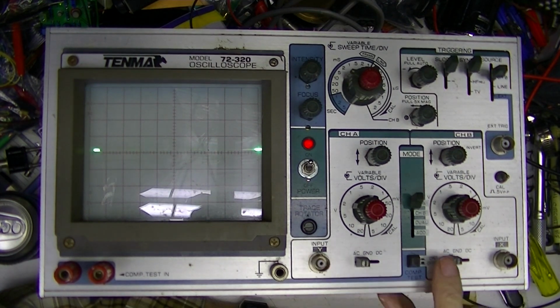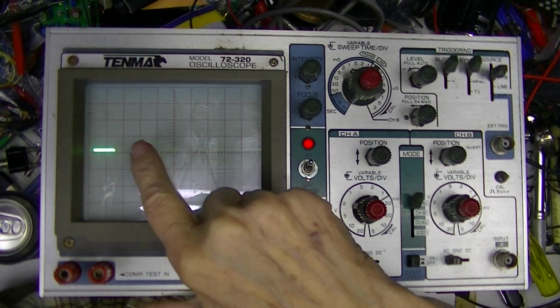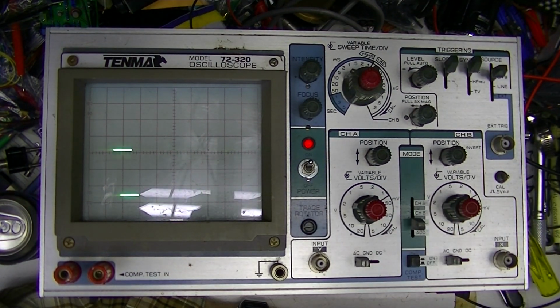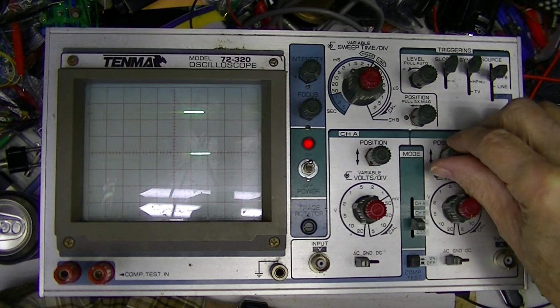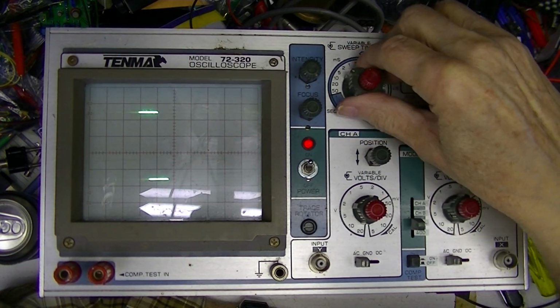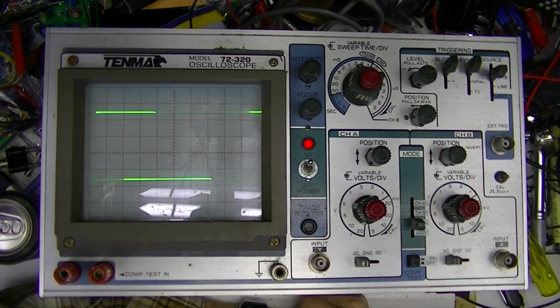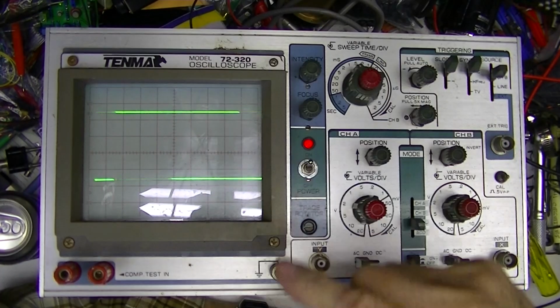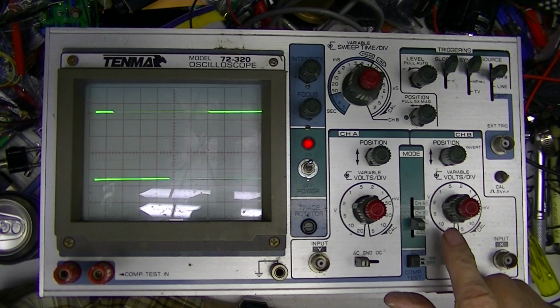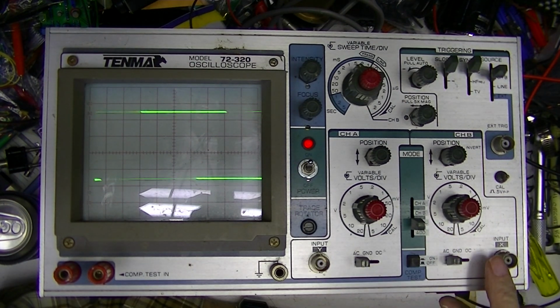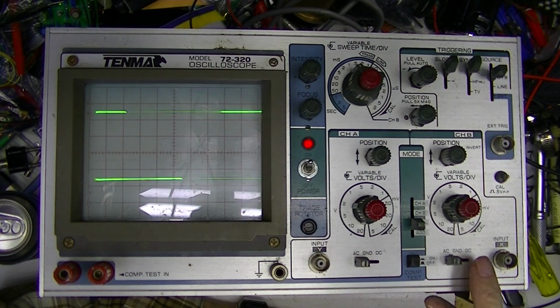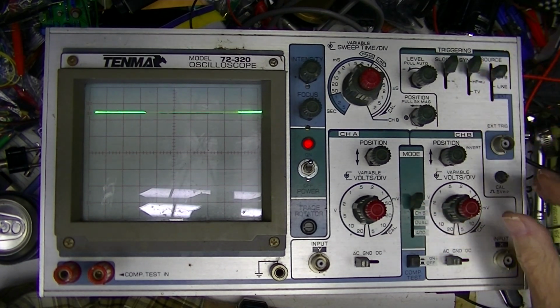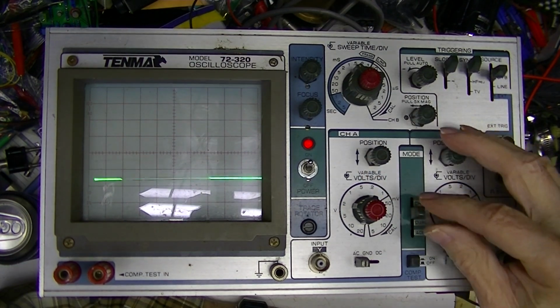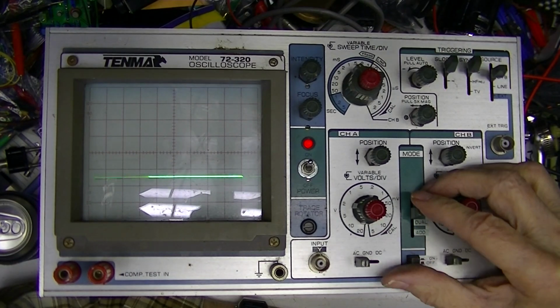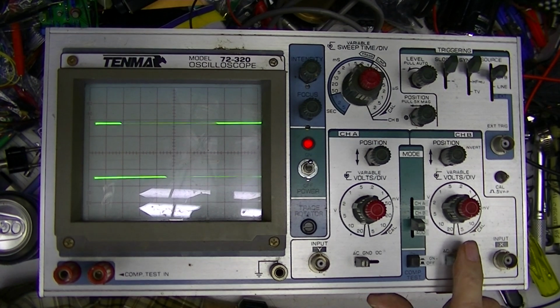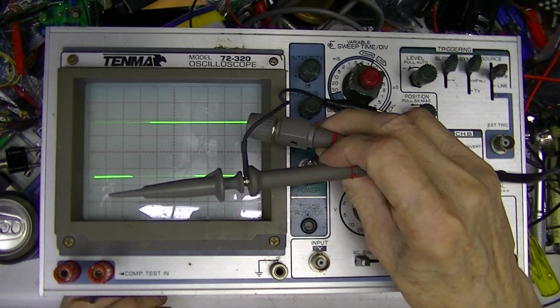This oscilloscope has two inputs, so it could have two horizontal lines. Like that. Speed changes a little bit. See, there's two of the lines now. Of course, there's no voltage applied, so there's no vertical deviation. And although it's called input Y and input X, it's the same as channel A and channel B. We can display only channel A. We can position it up and down. We can display only channel B and position it up and down. Or we can show both inputs on the screen. Provided you with two probes.